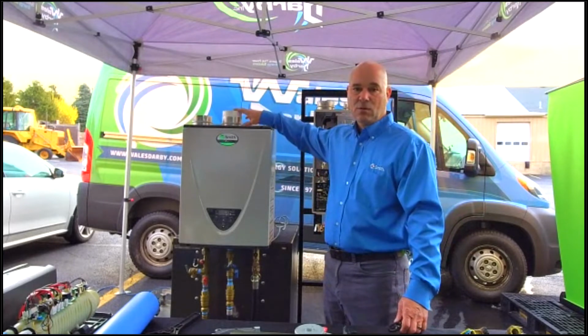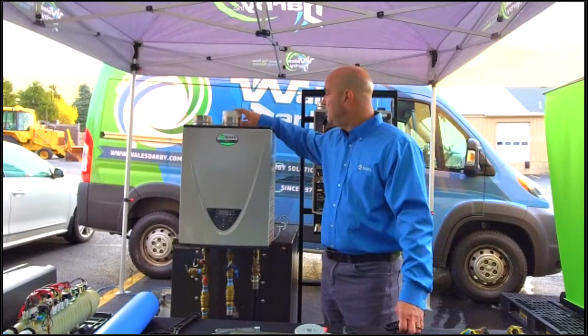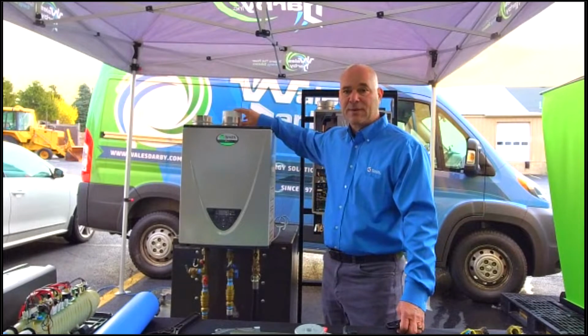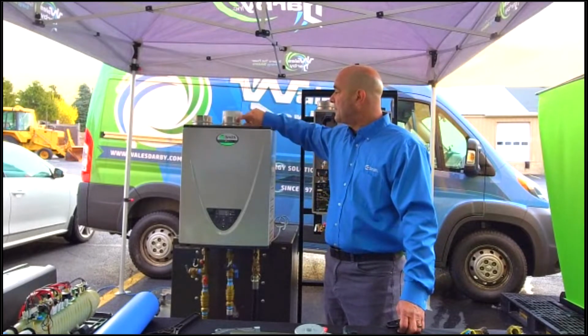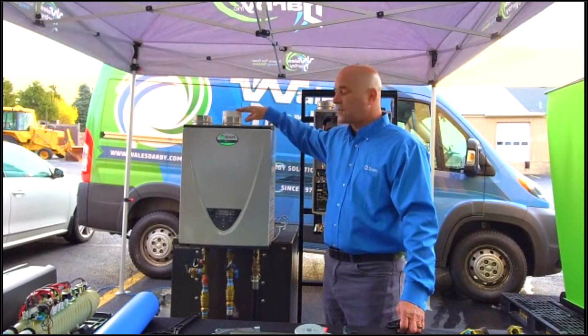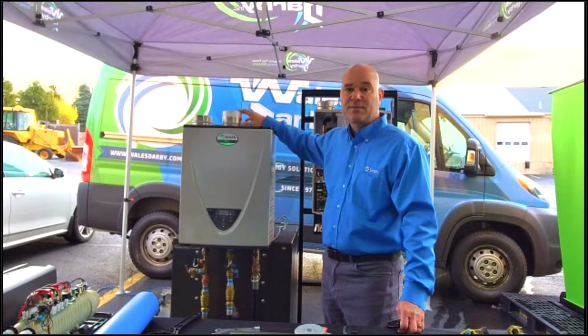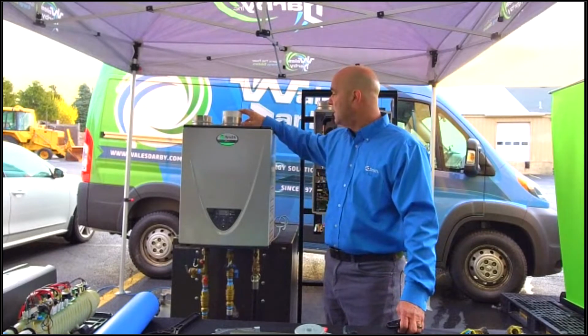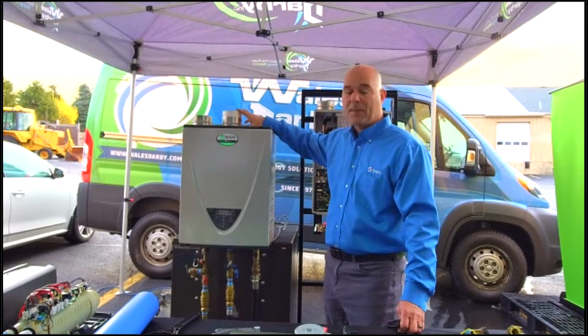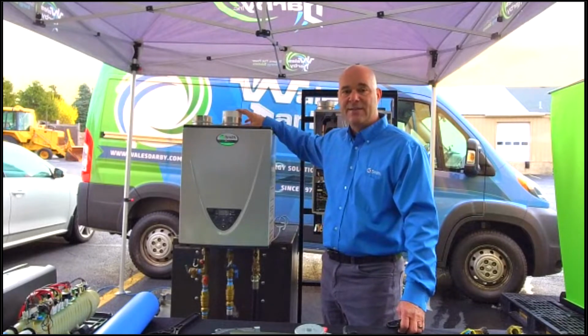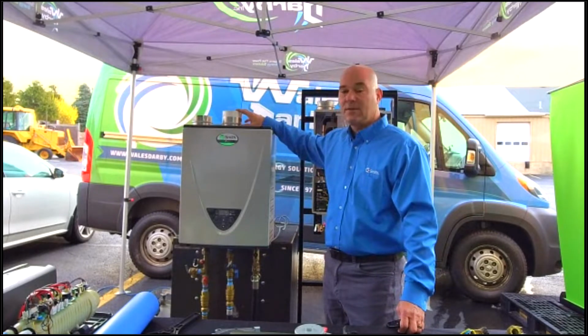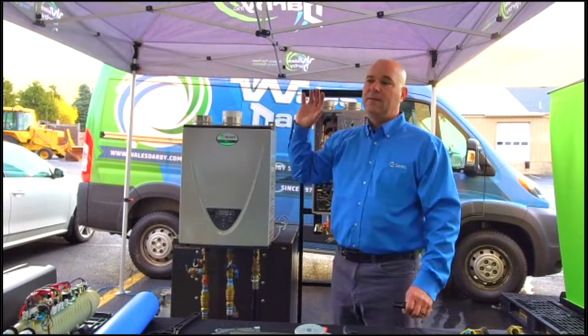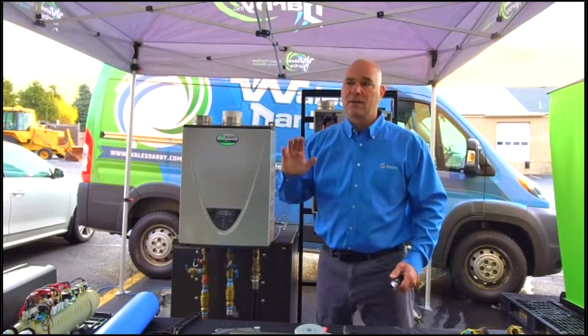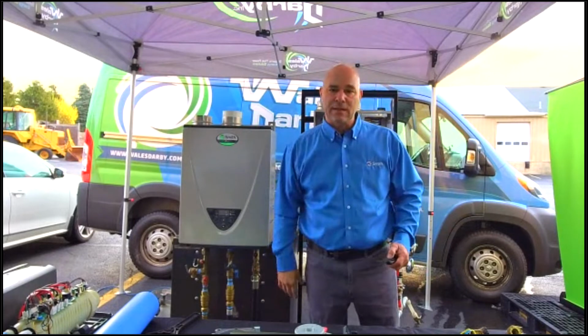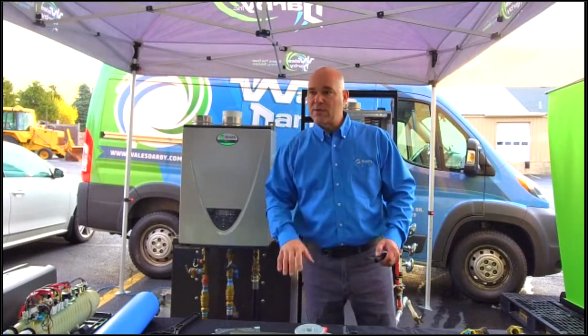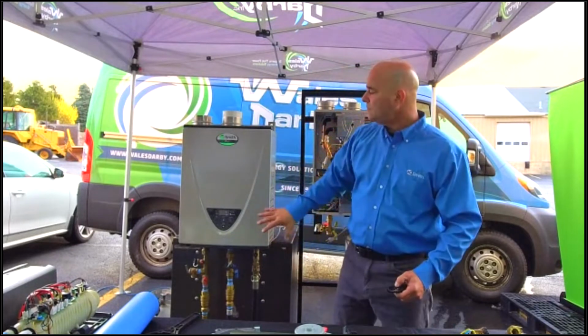PVC, stainless steel, or polypro venting. Polypro is probably your best venting option right now. Centrotherm, right off the top, they make an adapter. Centrotherm is going to be less expensive currently than PVC. So there's your venting options, up to 100 feet, depending on the size. This unit vents in 3 and 4 inch, and that's all going to be in the manual. I'm not going to go through every venting distance and such. We're going to spend more time going through the components.